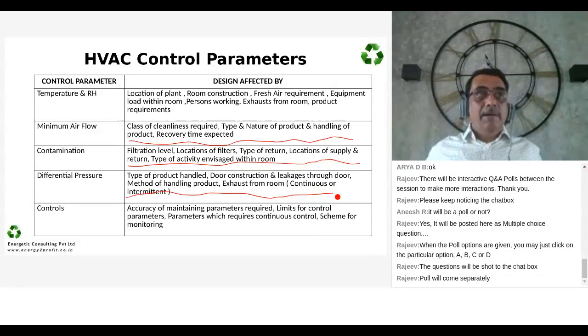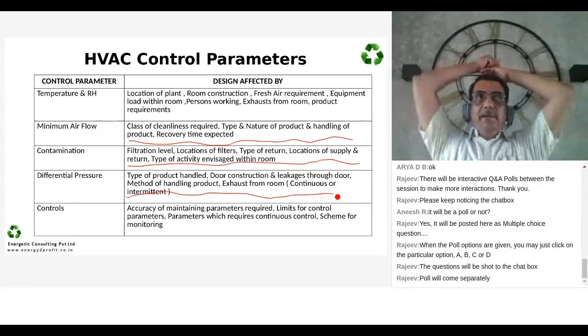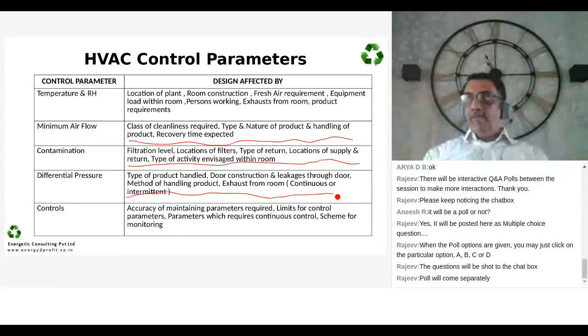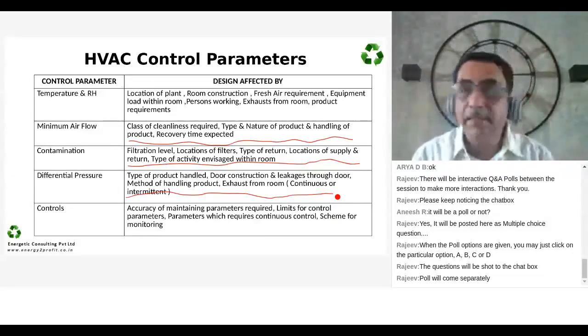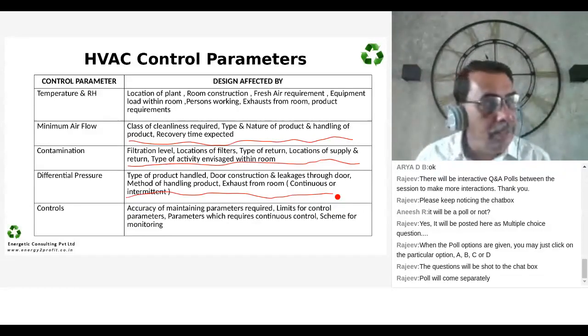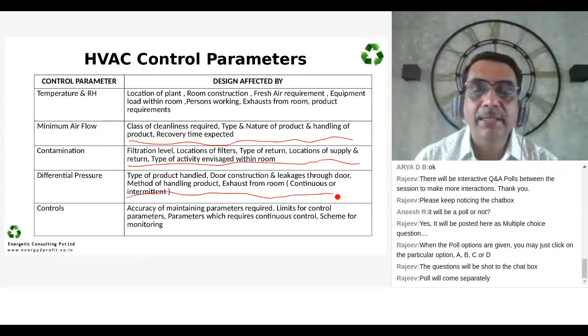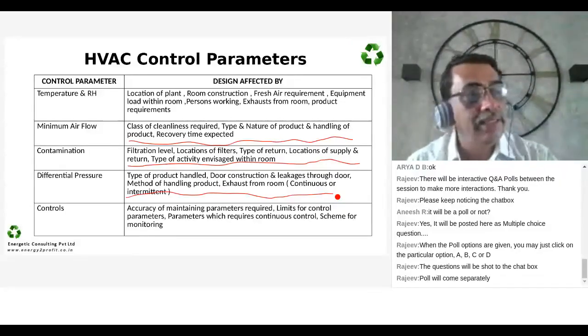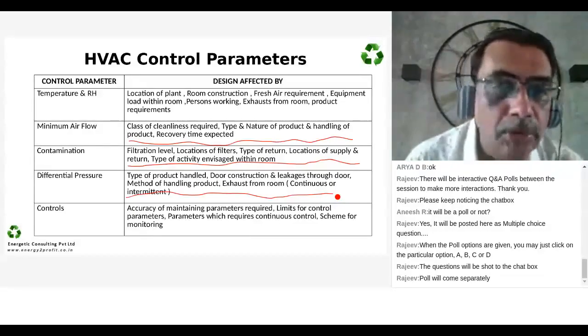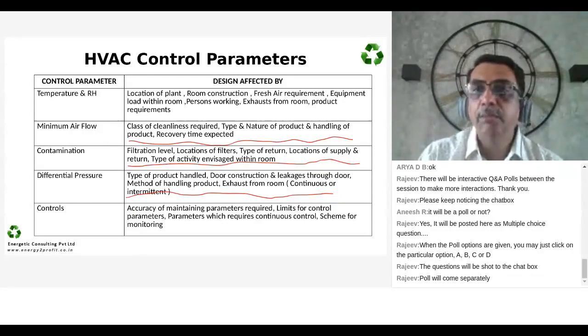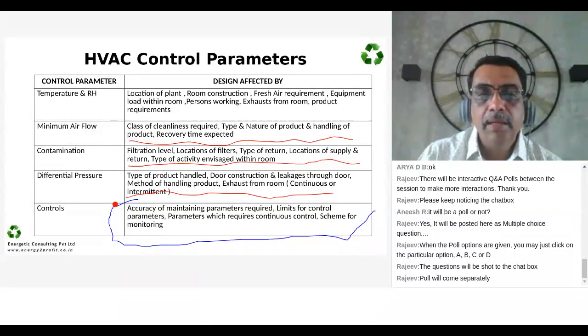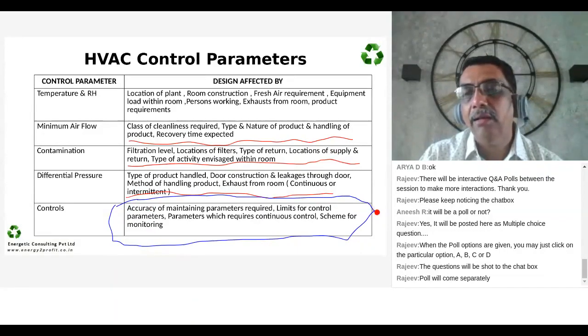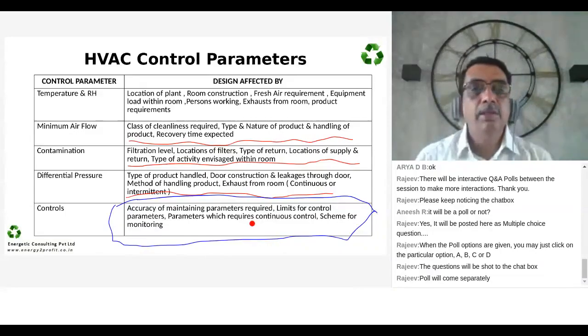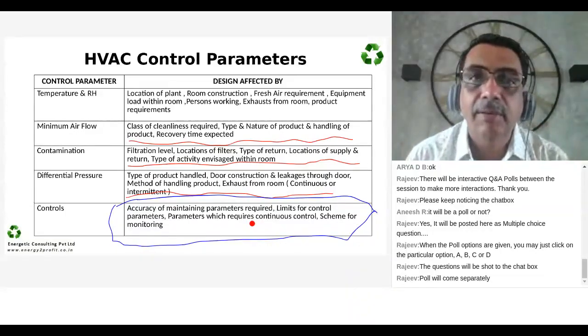Whereas if you are doing tableting, where the tablets are getting manufactured, you would like to have the manufacturing area at a higher pressure, because you would not like the dust from the surroundings to come inside the area. Now, these applications decide, for the same manufacturing area, in some cases you will have a negative pressure and in some cases you will have a positive pressure. Now, all of this has to be finally controlled. And control, when I mean, it is measurement, monitoring, and control. Not only measurement, not only monitoring. So these are the fundamentals of designing air conditioning systems.